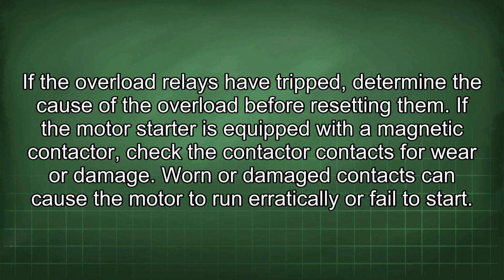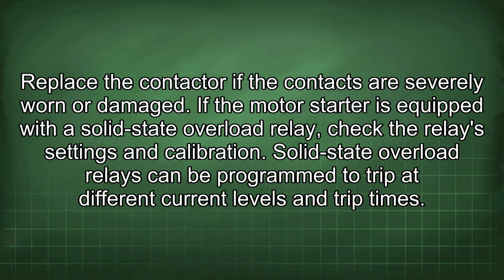If the motor starter is equipped with a magnetic contactor, check the contactor contacts for wear or damage. Worn or damaged contacts can cause the motor to run erratically or fail to start. Replace the contactor if the contacts are severely worn or damaged.